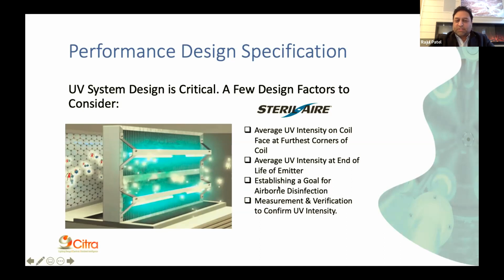That brings me to the next part: establishing a goal for airborne disinfection. In our experience, having audited hundreds of air handlers and rooftop units, including in the medical field, we find a handful of systems have UV in them. To date, we've never found a system where personnel at the site were aware of any goal or design basis. They simply don't have one. That's just not the way you can design a UV system. There must be some basis.